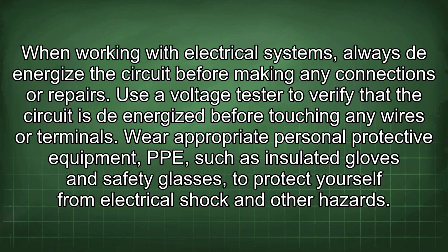When working with electrical systems, always de-energize the circuit before making any connections or repairs. Use a voltage tester to verify that the circuit is de-energized before touching any wires or terminals. Wear appropriate personal protective equipment, PPE, such as insulated gloves and safety glasses to protect yourself from electrical shock and other hazards.